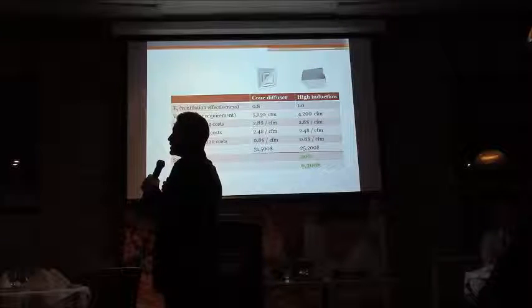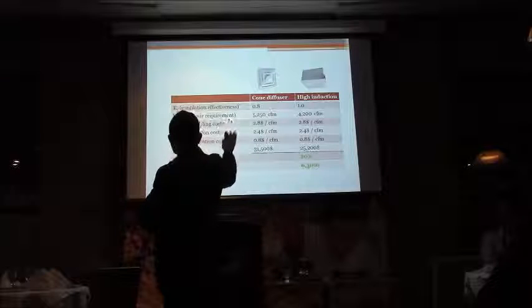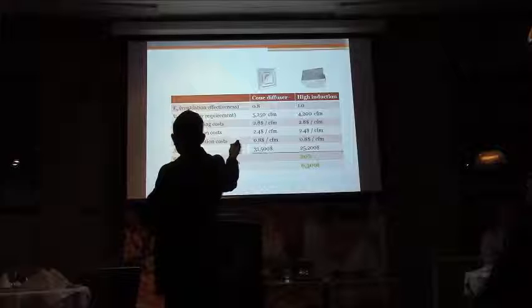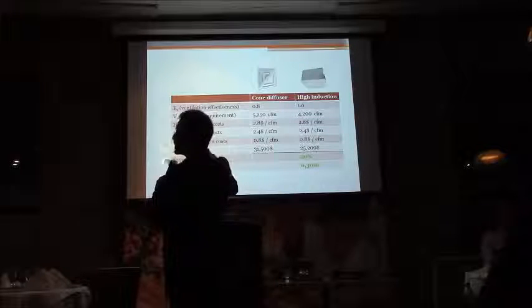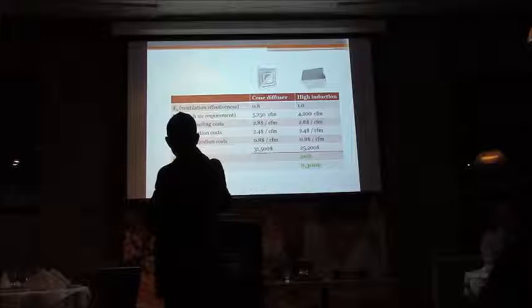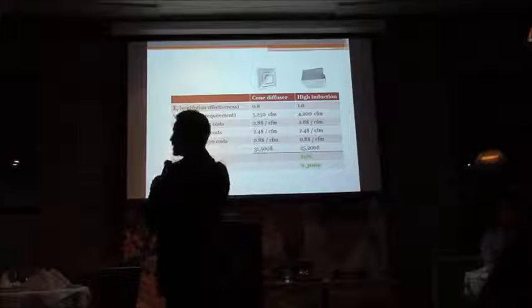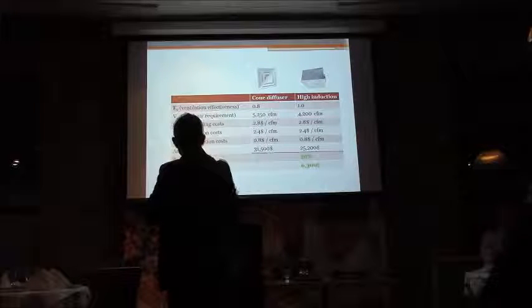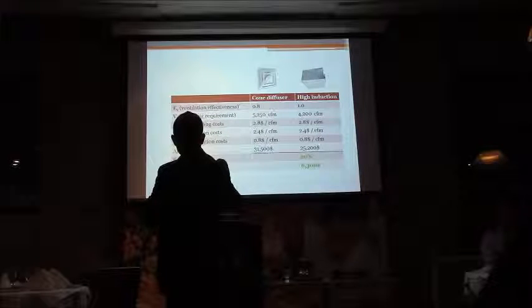So if we were at 4,200 CFMs calculated, then with high induction, with a 1.0 effectiveness factor, you stay at 4,200 CFM. At 0.8 factor, you have to be at 5,250 CFM of fresh air. So that's an annual cost of $31,500 to treat that fresh air, compared to 25,200 CFMs. And the savings would be 20% for a total of $6,300 per year.